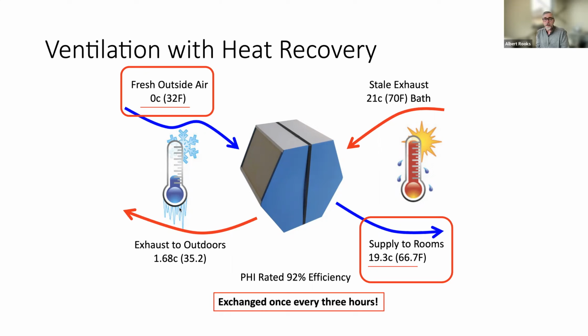exchanger. At the same time, the upper right-hand side has the conditioned air coming back from the kitchen and bathroom or the exhaust locations of the building. So it's warm, it's got some energy. And we bring those two streams of air right next to each other. They don't touch each other. They're going by plates. It's a plate heat exchanger. So warm air is passing in from the upper right. Cold air is passing in through the upper left. Actually, I think it would, and they're going to meet in the middle of the heat exchanger.